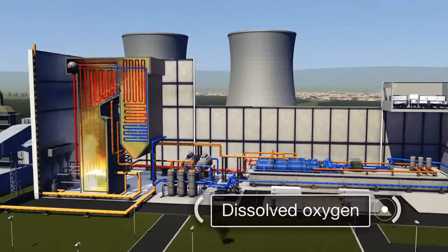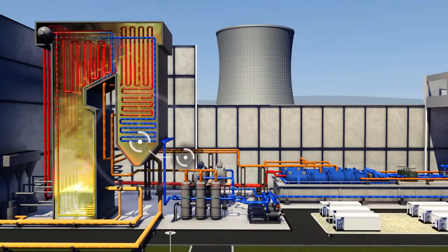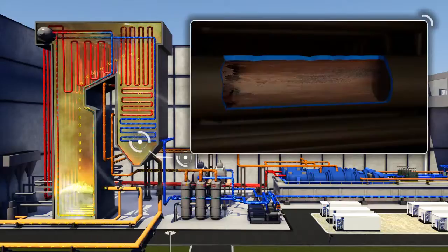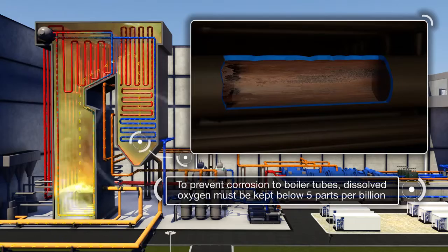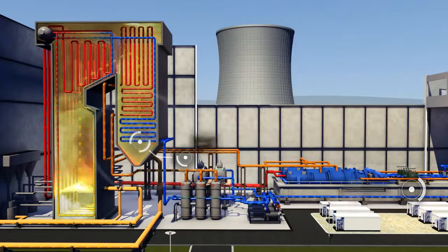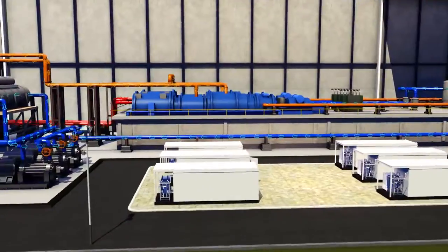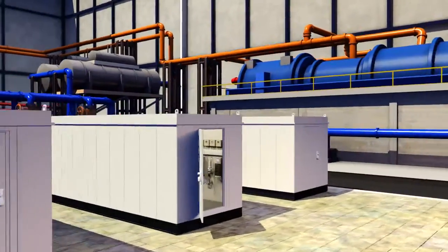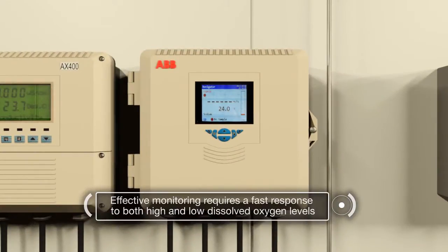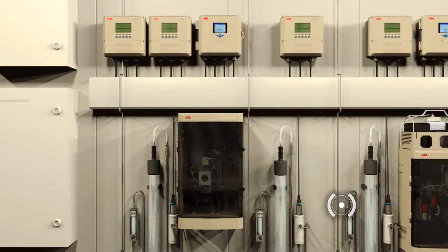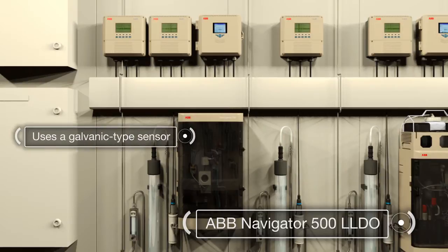Dissolved oxygen is highly corrosive to most metals, especially the mild steel used for boiler tubes. To minimise its impact, its levels need to be reduced to 5 parts per billion or less. The dramatic variations in oxygen levels during the load cycle of a plant require an analyser offering a fast response across both high and low dissolved oxygen concentrations.